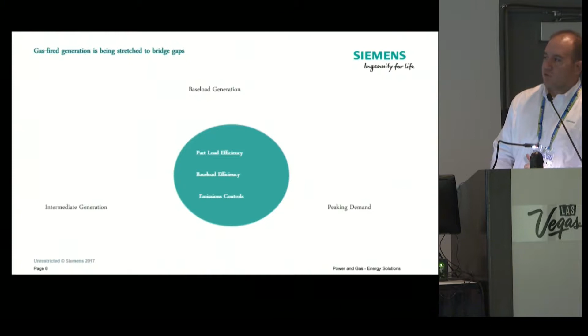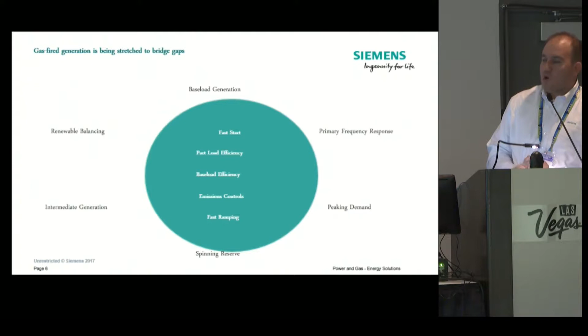We have some technologies, like clean ramp, that allow you to tap into those market spaces. And now combined cycles are being stretched even further - renewable balancing, primary frequency response, spinning reserve with a combined cycle plant. Things combined cycle plants were never meant to do, they're being required to do now.